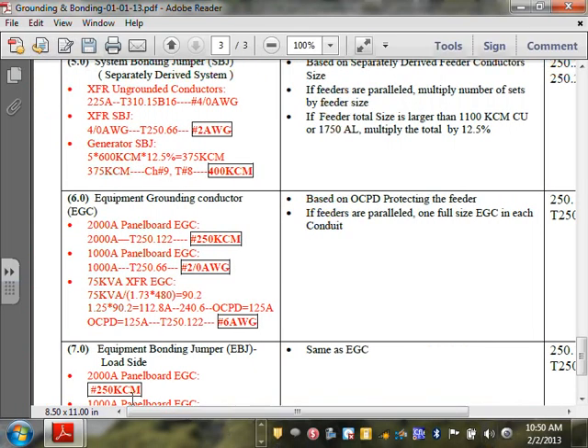Straightforward, right? And how many of them do you have to put? As many as you have runs. So this is not just one conductor. This is a 2/0 conductor, as many as runs. So if I want to parallel these, this is 1,000. Say I want to pull 4 runs, 250 amps. So 4 runs for this 1,000 amp switchgear. Then I need 4 conductors. What's the size again? 2/0 in each one of these conduits. Everybody's okay with that?